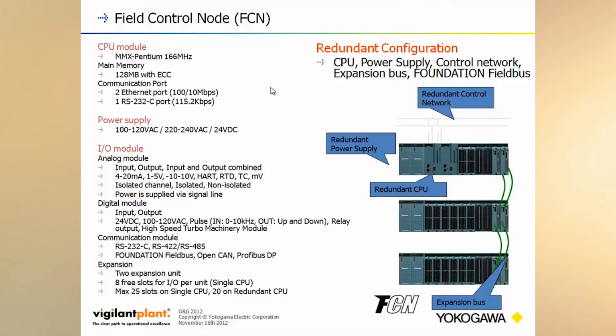So for the analog modules, you're typically going to see 16 for your currents, voltages and thermocouples, and 12 for your RTDs per module. And we have a choice of isolated, non-isolated, channel isolated. So it just depends on what you're looking for in that I/O. We can also do two-wire devices off these and power them through those two wires, so there's built-in power across the backplane to power up your I/O modules for true two-wire instruments.